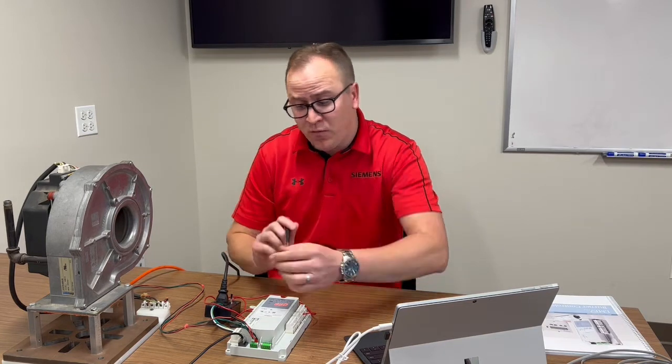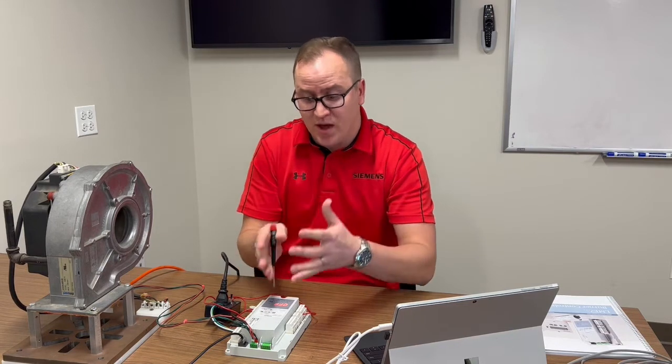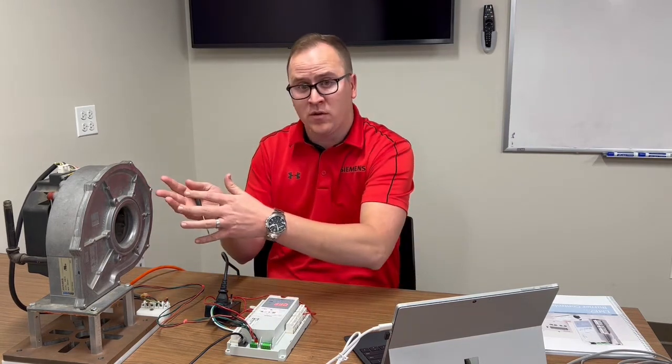And these four wires are: there's a 24 volt DC signal, there's that PWM signal going out, that tachometer signal coming back, and a ground wire, all with these four wires.